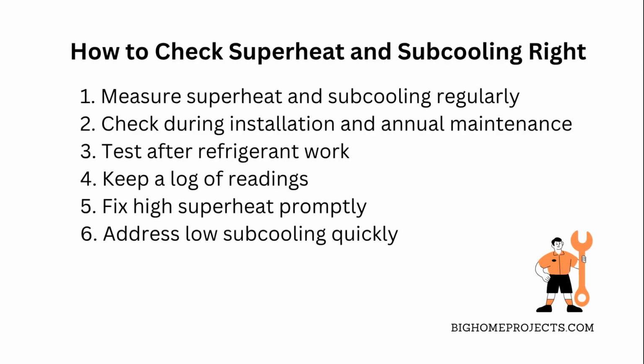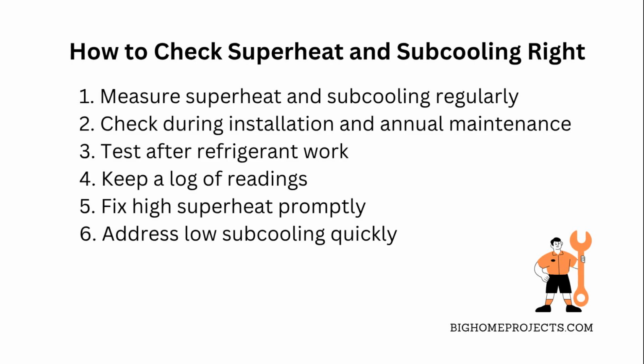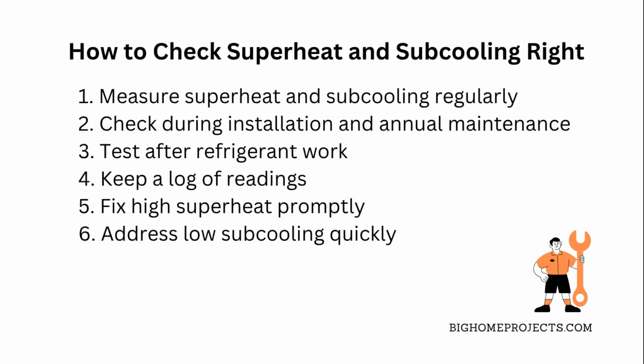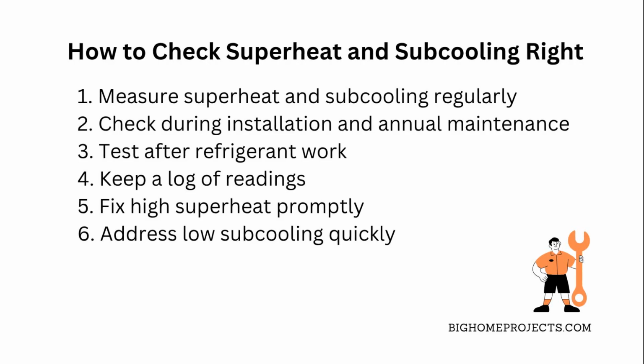Superheat and subcooling are all about making sure your air conditioner or heat pump is working right with the refrigerant. Superheat measures how much the refrigerant vapor heats up after it evaporates, while subcooling checks how much the refrigerant liquid cools down after it condenses.